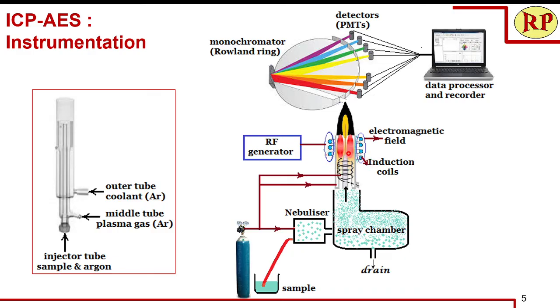Around the plasma torch we have induction coils — that is why we call it inductively coupled plasma, because the plasma is created due to the heat created in the induction coils. When the radio frequency signal is generated by the RF generator, an electromagnetic field is formed around the plasma torch, which helps in the formation of the plasma.